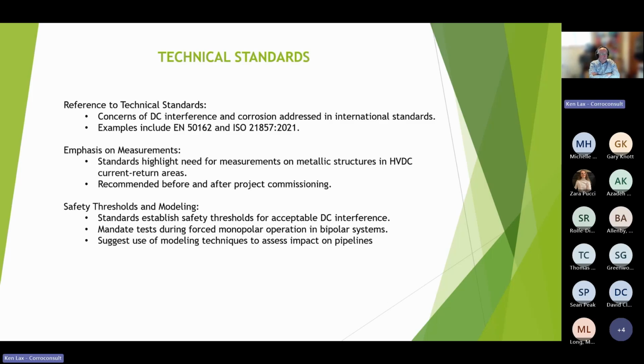There isn't a great deal of help in the technical standards at the moment for HVDC modelling and mitigation. There are some examples which I've put up there, 50162, 21857, but really there's not enough in there to give you a good steer. The other thing to bear in mind is that the safety thresholds the HVDC people adhere to are not necessarily good for us, because, as I mentioned, the difference between a freely corroding pipeline and one that's fully protected is less than a volt. If you're running a 33,000 volt DC system, you're not going to worry about the odd volt here and there. So we have to be aware of that.